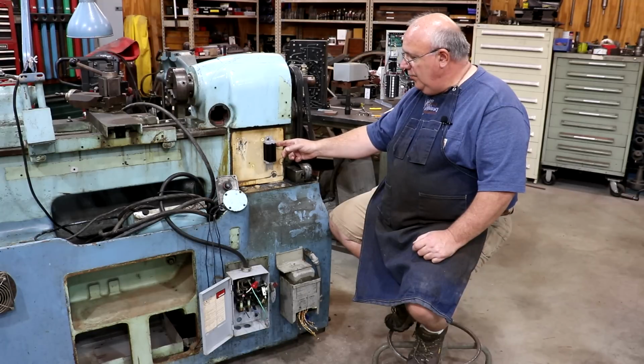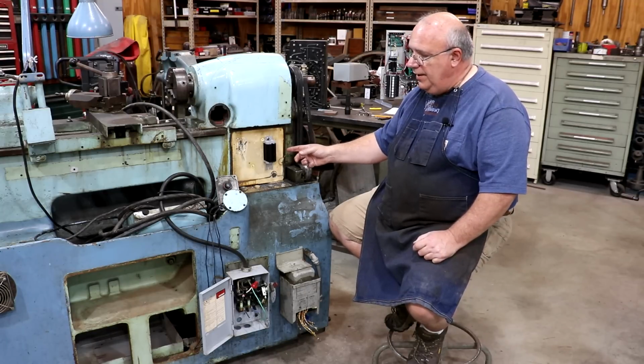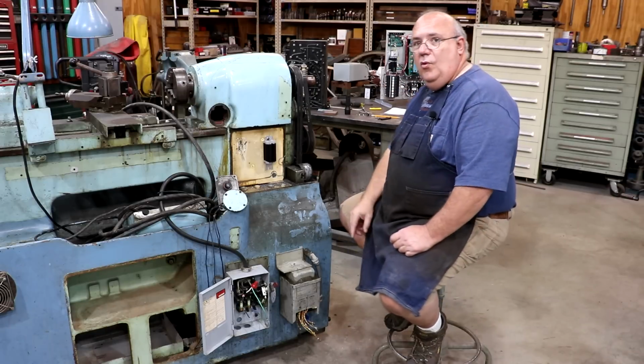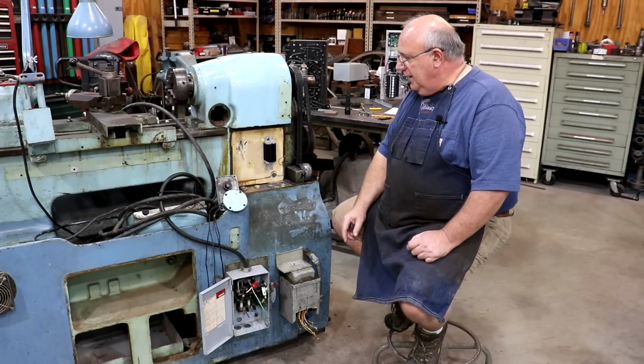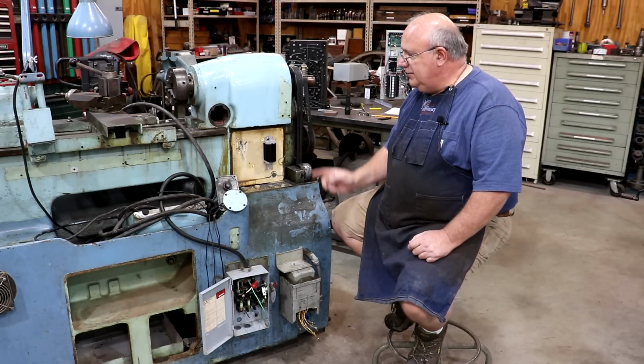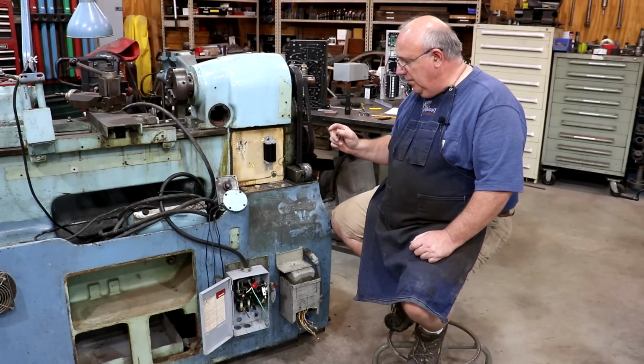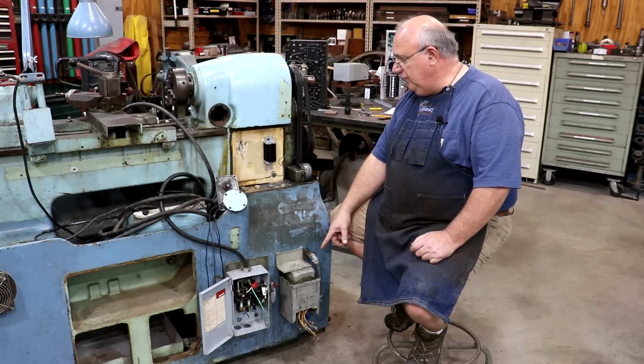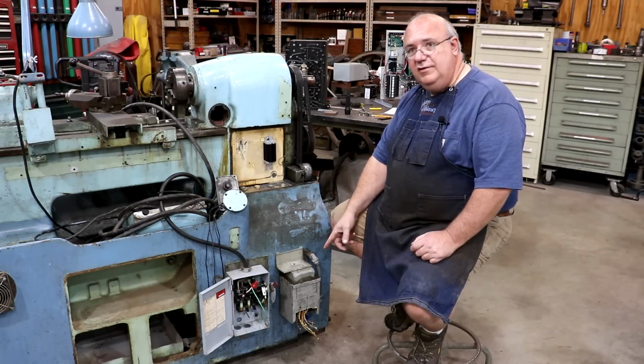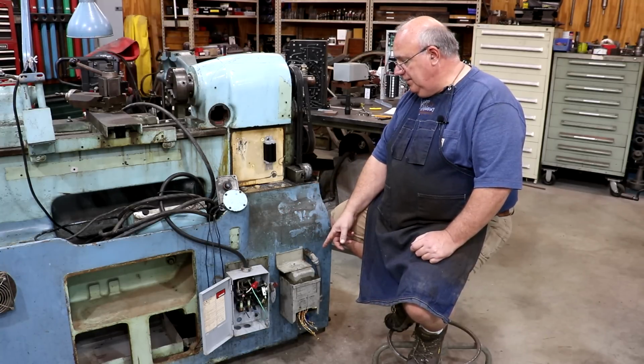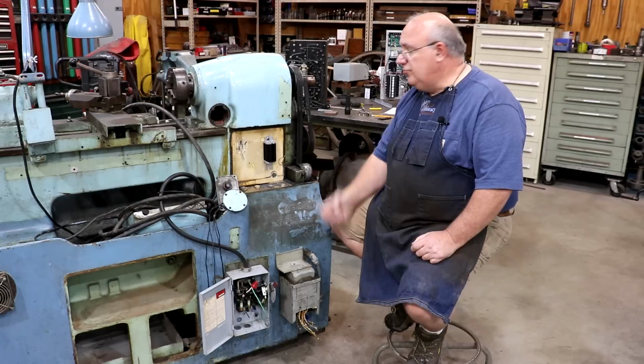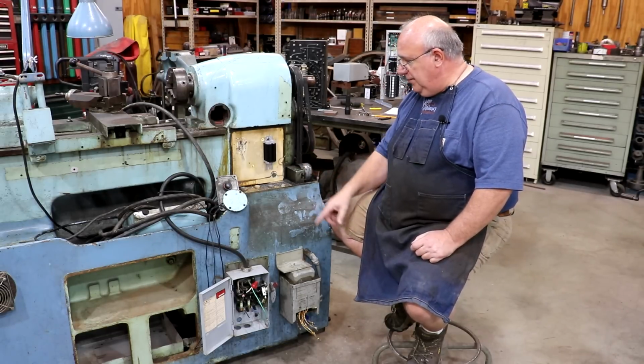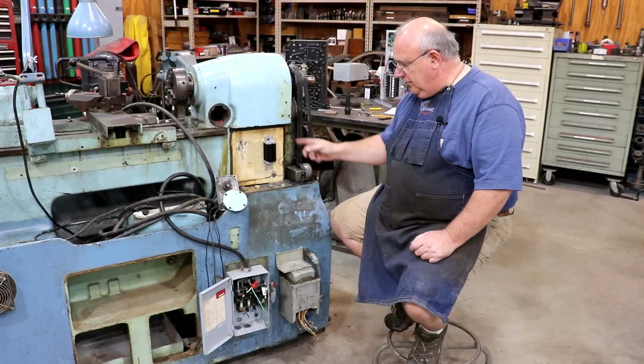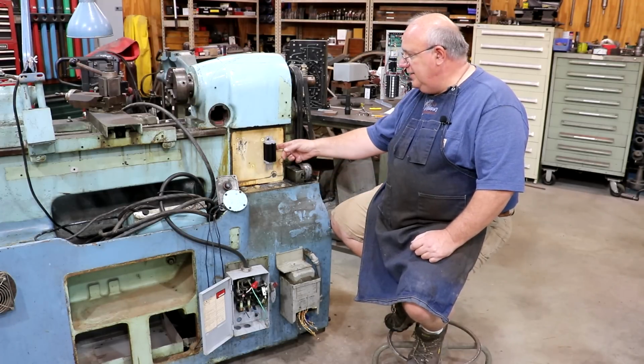L1 and L2 will go from the terminal block to the control board to provide power, and then some fused power will come back from the board down to the transformer, which converts that 220 volts to 110 volts alternating current for our control circuits. The transformer wires will come out, then come back at the other voltage through the control block again.